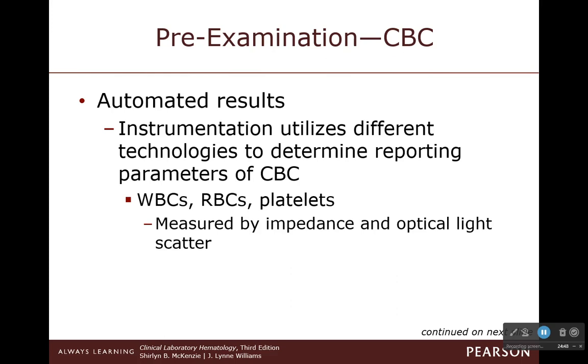It has a standard. Basically, you measure the standard, and then when you put your lysing reagent in, it makes the cells lyse, and then the spectrophotometer gives us our hemoglobin concentration. Okay, so those 4 things are actually measured. And there's another thing that we'll talk about.